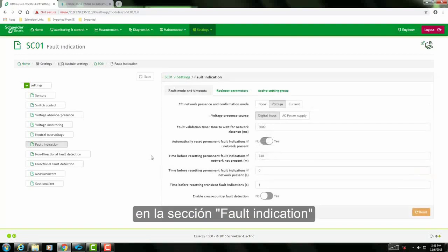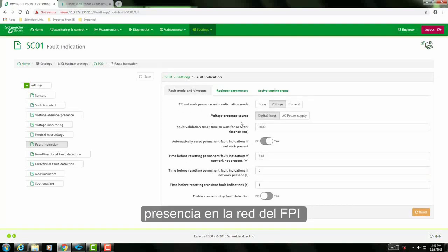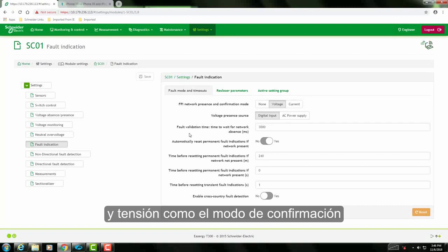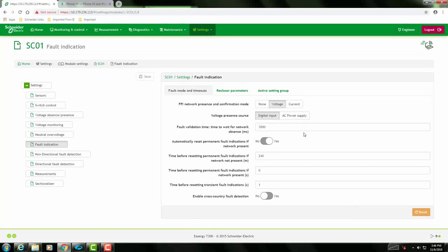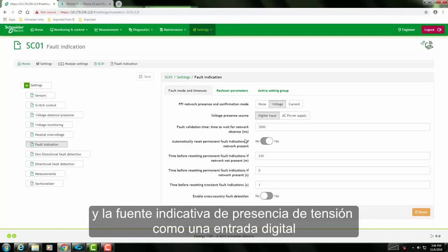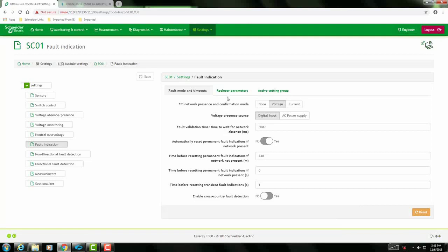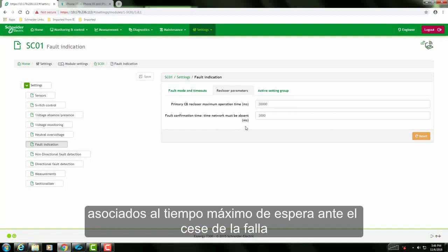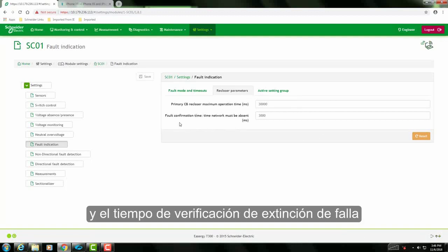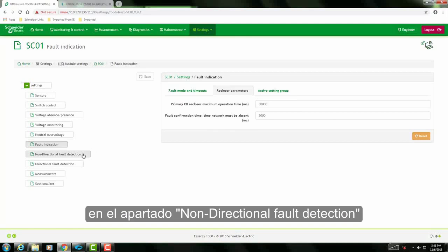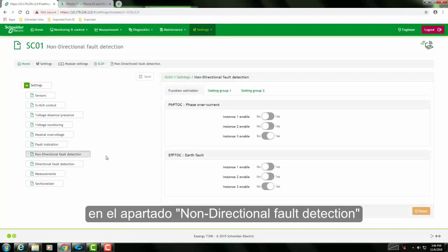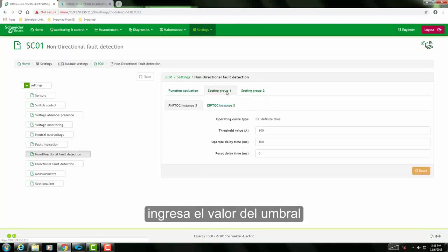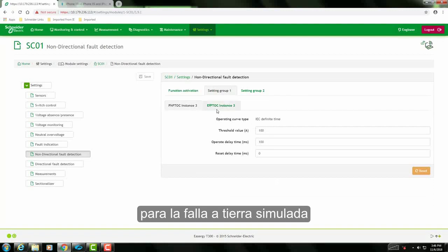In the fault indication section, we have chosen FPI network presence and confirmation mode as voltage, and the voltage presence source as digital input. Enter recloser parameters, i.e., primary CB recloser maximum operating time and fault confirmation time. Under non-directional fault detection, enter the threshold value for simulating earth fault or phase fault as per your requirement.